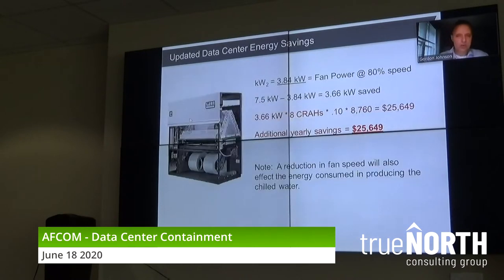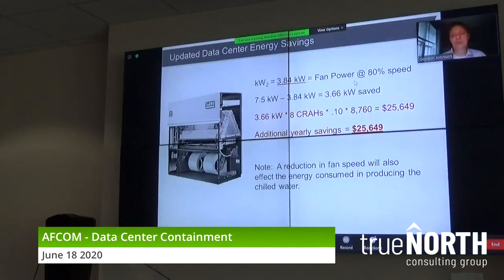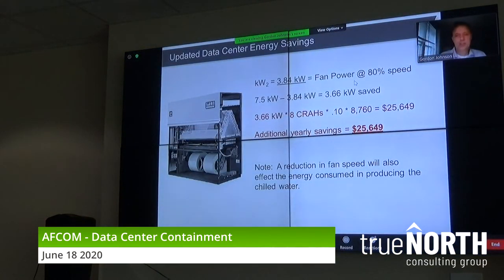cost. So here, we only have 8 CRAH units, but if you look at that third line, if you take that savings in kW times the number of units times the cost of electricity, 10 cents a kilowatt hour, times the hours in a year, we just saved an additional $25,649. Now, some data centers have 40 or 50 CRAH units. They're a lot bigger. They're consuming a lot more power at 100%, and knocking them down to 70%, right off the bat, some data centers save $100,000 or even more by reducing that fan speed.